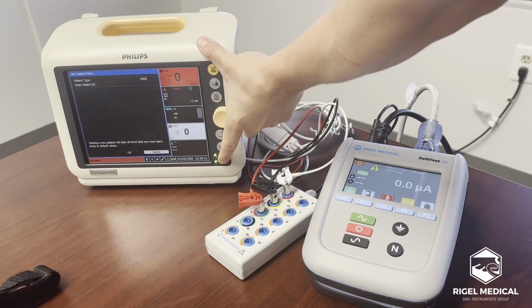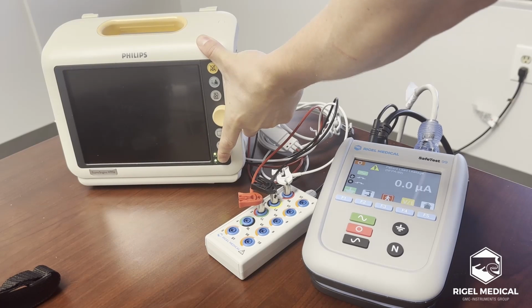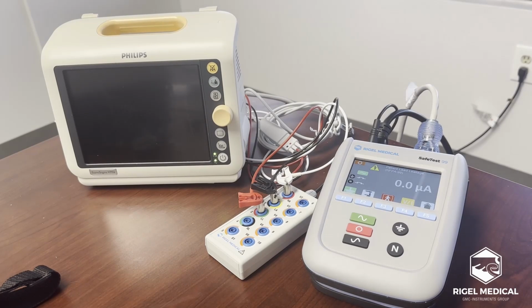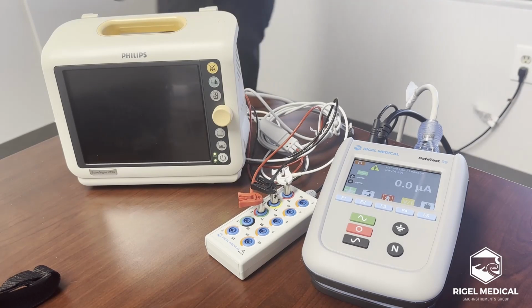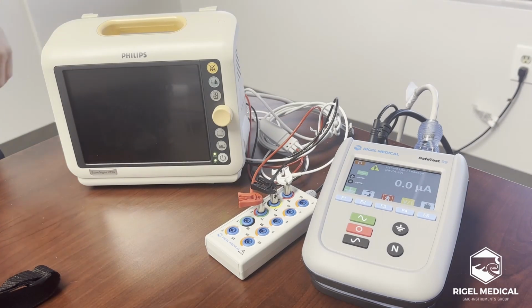Medical devices are typically developed to have very high levels of isolation, particularly for the ECG connections, so you're unlikely to see high levels of leakage. But you've got a significant limit for NFPA 99, so you're unlikely to see high measurements unless you've got a fault within the device.